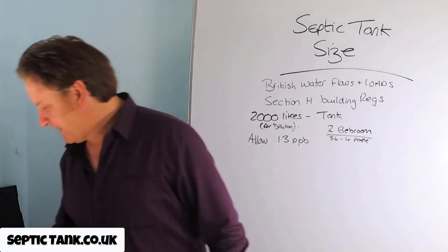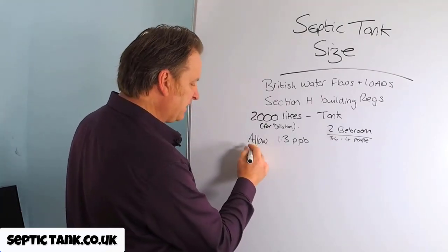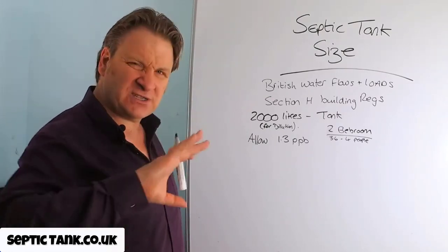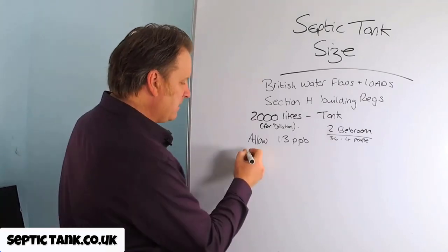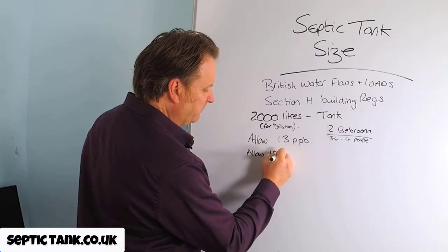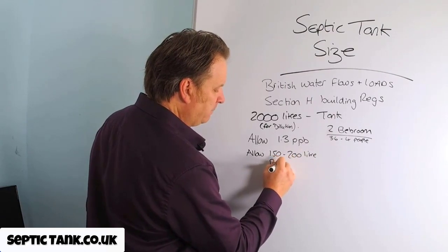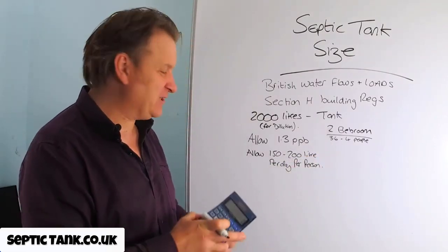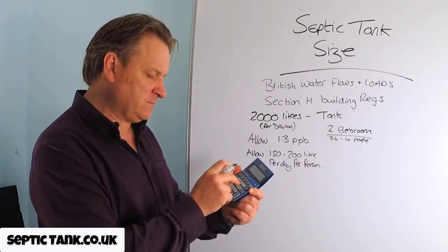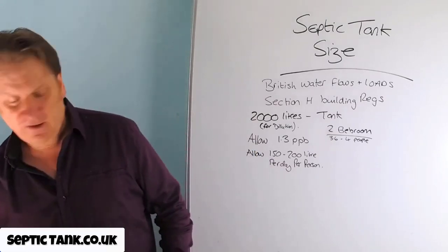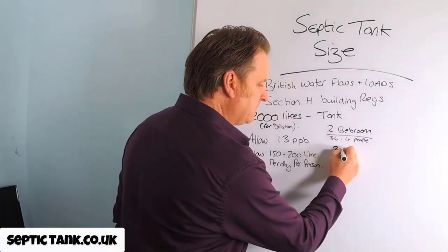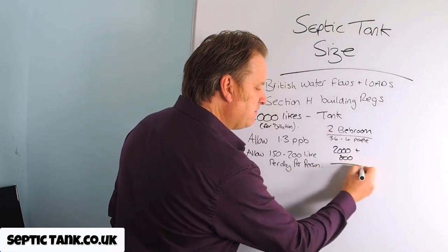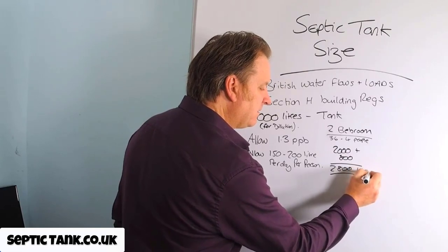We then need to get our calculator because British Water states that in a domestic property — a standard domestic house where you and I live 24/7 — you are to allow anywhere from 150 to 200 litres per person per day. I'm going to err on the side of caution and go for 200 litres. So we've got four people: four times 200 equals 800 litres. Take our base figure of 2,000, plus 800, and we would need a minimum of a 2,800 litre septic tank.